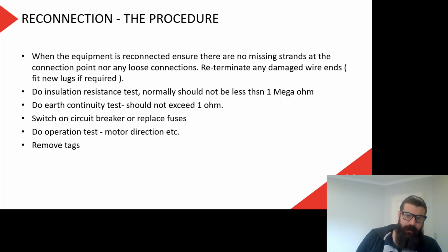When the equipment is reconnected, ensure there are no missing strands at the connection point or any loose connections. Re-terminate any damaged wire ends and fit new lugs if required. Look, that's just good work practices, right? So make sure all our connections are good, make sure they're tight, make sure there's no little bits of copper flying around, make sure we haven't stripped it too long and there's bits of copper hanging out of the terminal. As we go through the course and do more wiring tasks, you'll get much better at that and understand what a good connection looks like.